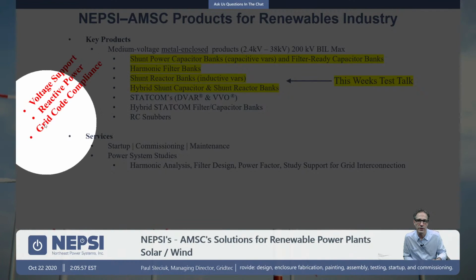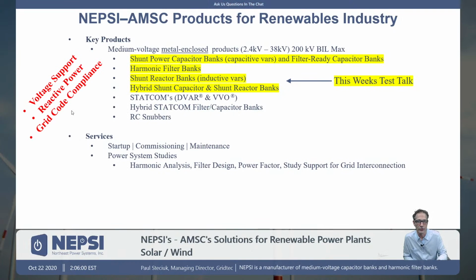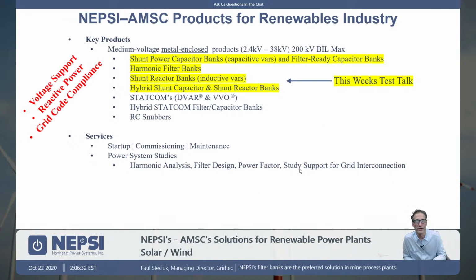So if you're a renewable power plant, you're interconnecting onto a larger electrical grid, you need to have grid code compliance. And there are typically interconnect studies that are conducted by engineering firms. They dictate the amount of reactive power you need to meet certain criteria within the system. Incidentally, NEPSI can be involved with the harmonic analysis and with filter design and the power factor study portion of it. And now that we're part of AMSC, we can also have support with their planning group for the study support for grid interconnect studies. So we are basically providing almost a full turnkey of options for the renewables industry.